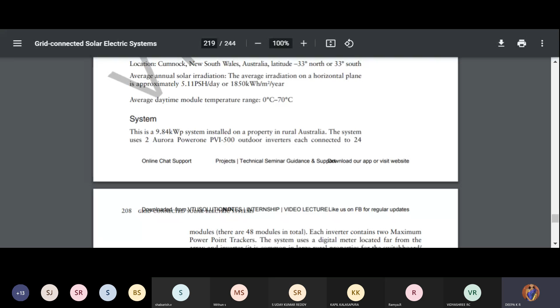So 24 means, you can see, there are two Aurora Power-One inverters. Two means two separate inverters, and each inverter is connected to 24 modules. So 24 plus 24, how many modules? Totally 48 modules of PV system we have. So these 48 are segmented in two parts: 24 is one segment, another 24 is one more segment. The conversion of DC to AC is done by using an inverter, that is the PVI 500. So the company Aurora Power-One PVI 500 has been used.